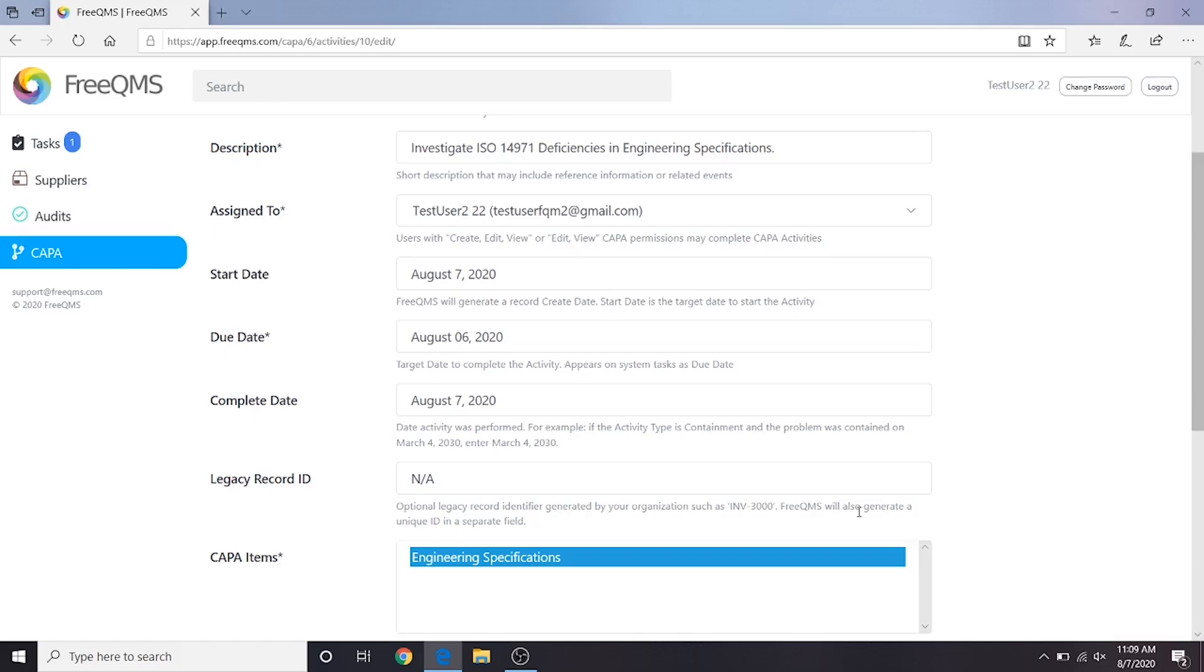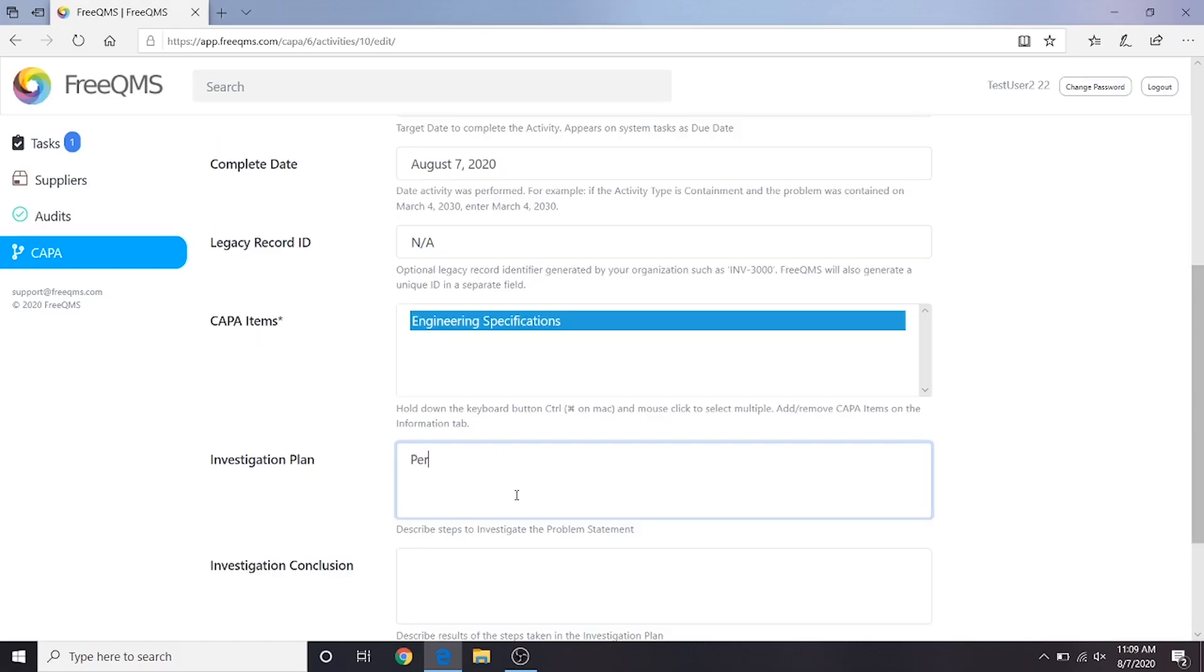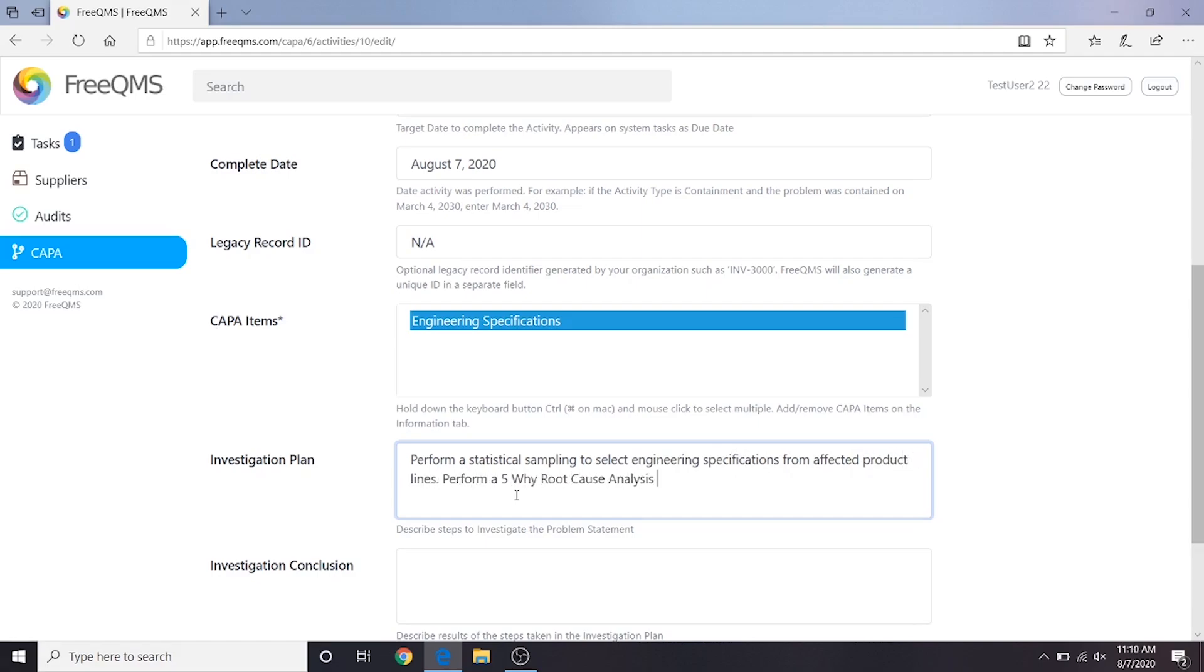For our investigation plan, we will put: Perform a statistical sampling to select engineering specifications from affected product lines. Perform a 5 Why root cause analysis to determine deficiencies in addressing ISO 14971.